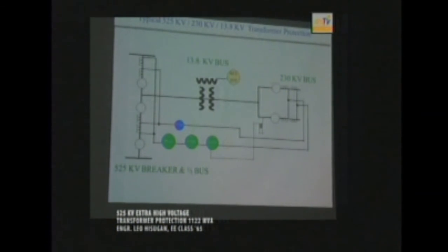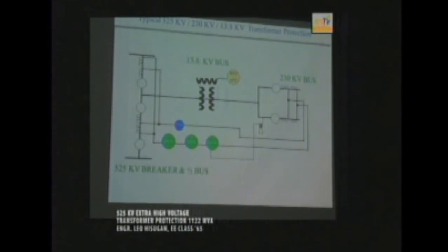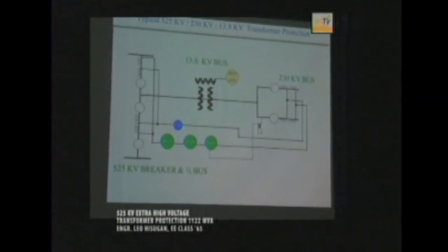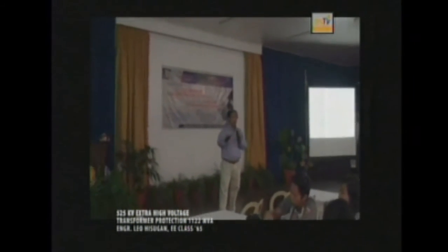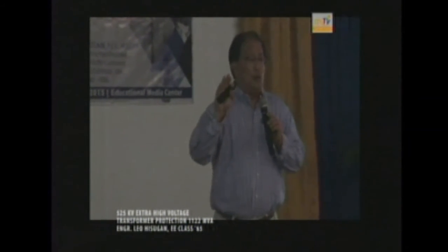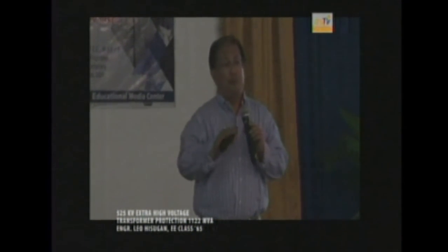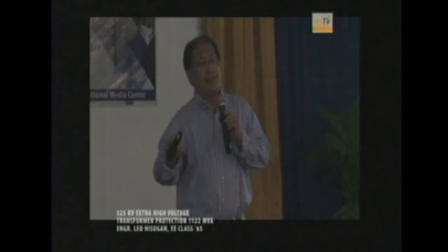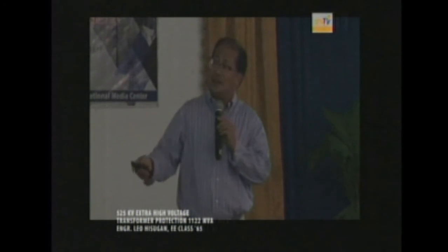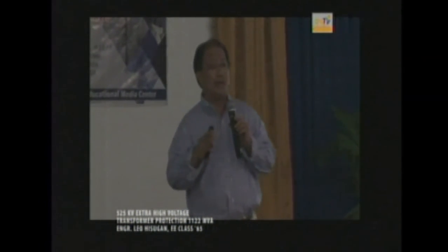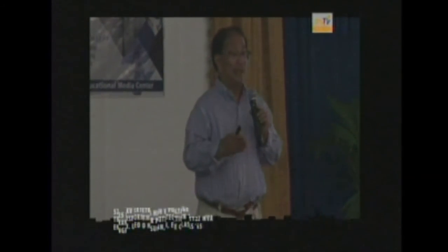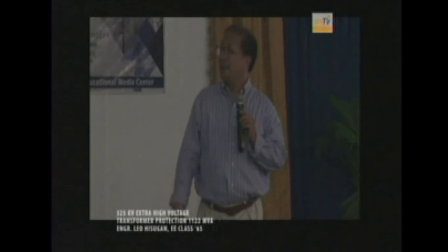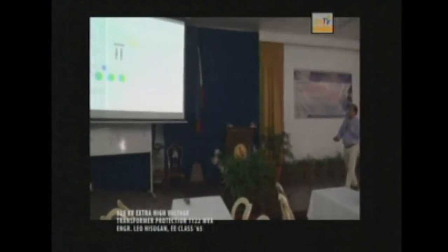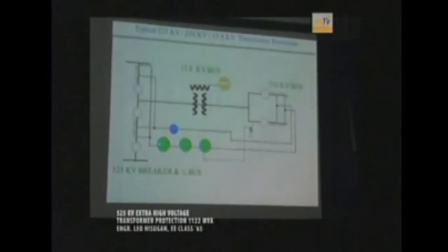So on the 525 kV transformer protection, we have the transformer differential, the set A, for example, and the set B protection. So the set A protection is, for example, a GE relay. The set B protection is an SEL relay. When we speak of set A and set B protection, they are fully redundant. Meaning, whatever set A relay protects, the set B relay also protects at the same time. So they have the same protective functions or elements embedded in them. So if this is your transformer differential here, you have set A and set B here.